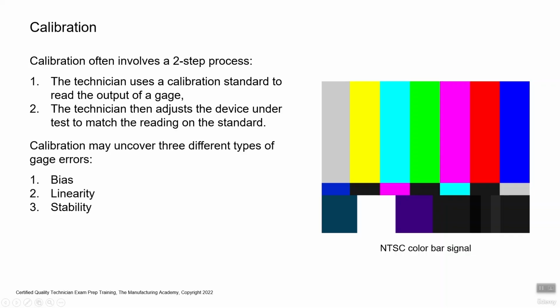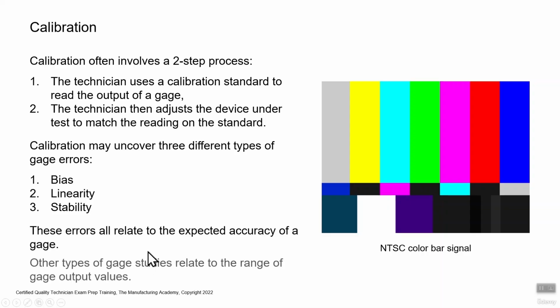So calibration may uncover three different types of gauge error. We're not going to do a lot with these here, but bias is a systematic error. In other words, if your micrometer is consistently reading 5 millimeters too long or 0.5 millimeters too long, always measured wrong in the same direction, that would be a bias. Linearity has to do with a percent variation over the span of the scale. So let's just say you're talking about a weight scale and it's off by 1%. Well, at 100 pounds, that's 1 pound. At 500 pounds, it's 5 pounds. In other words, it's growing. It's getting worse over the span of the gauge. Stability has to do with its accuracy over time. This month, next month, the following month. So all of these track, again, different types of errors, and they all relate to the expected accuracy of the gauge. I think that's pretty well understood.